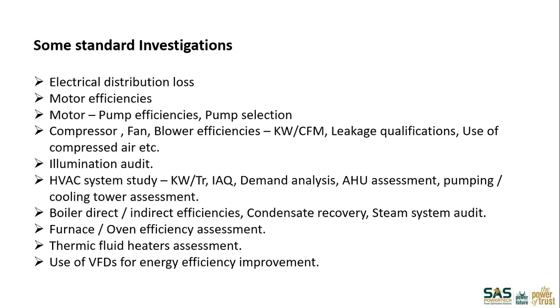Thermic fluid heaters are also used where higher temperatures are required. Steam can be used up to around 140, 150 degrees. Beyond that, if the process requires higher temperatures, then thermic fluids are used. So those heaters also can be analyzed for better efficiencies. Then there is the use of VFDs for energy efficiency improvement. This is again a very tricky game, but most of the time we try to convince the client in another way: this is not the application for a VFD, is what we have to tell him. For energy saving, if you require variable speed, obviously a VFD will have to be used, but energy saving may not always come if you use VFDs. So such analysis also comes under basic investigations.